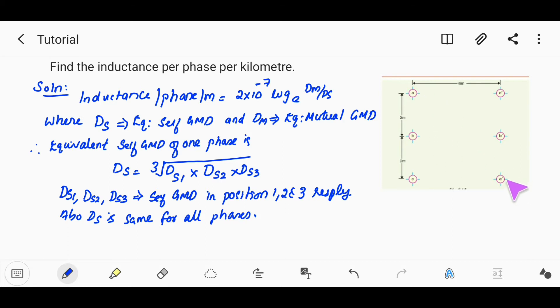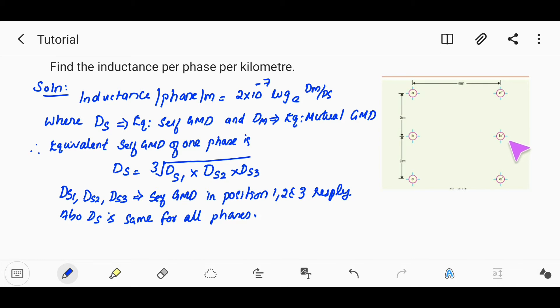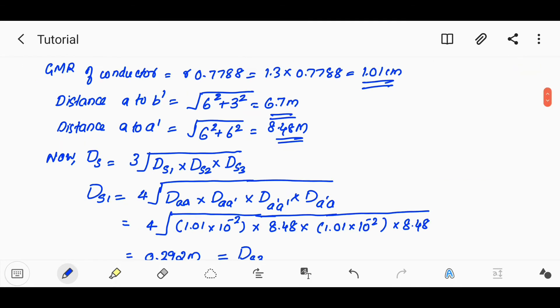A to A' and C to C' are the same distance. C to B' and A to B' are also the same. The GMR of the conductor is R × 0.7788, which is 1.3 cm × 0.7788 = 1.01 cm. The distance from A to B' is also computed.